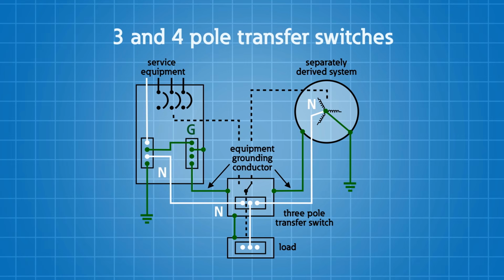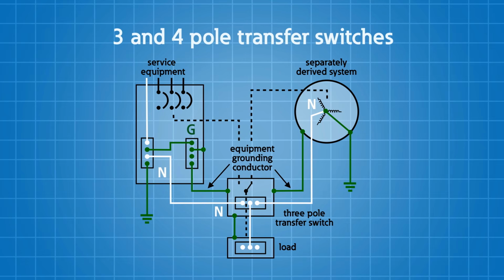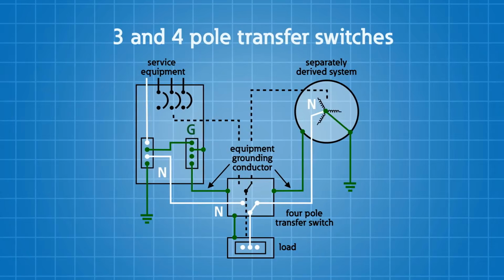So when I have a neutral conductor bonded and grounded in two separately derived systems, remember I have it grounded and bonded in my service panel, I have it grounded and bonded in my generator, I need to make sure that I only have one place where that occurs, and to get that done, I need to switch the neutral in the transfer switch. So that means I would need to have, say for example, a 4-pole transfer switch. If I do that, I put a 4-pole transfer switch in, I switch the neutral, everything is fine. A separately derived system implies that you would have a grounding electrode system and you would bond the neutral, the grounded conductor, in the generator with that system. If you have a separately derived system, the implication is that the transfer switch must switch the neutral with a 4-pole transfer switch.